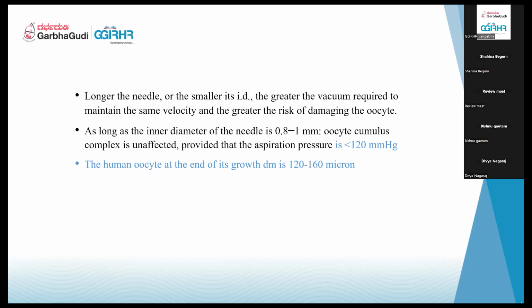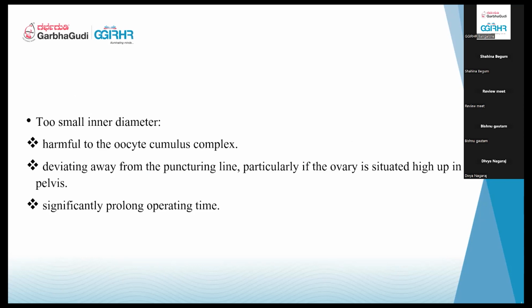If you take a needle that is smaller than that, if you go for a 19 gauge needle, obviously it becomes smaller, where the aspiration might not work, and then the oocyte gets disrupted completely. So then you won't get the complete oocyte. So therefore, having an inner diameter of 0.8 to 1 millimeter is sufficient. What happens if there is too small a diameter, or if you go for a higher gauge needle, it is harmful to the cumulus complex.